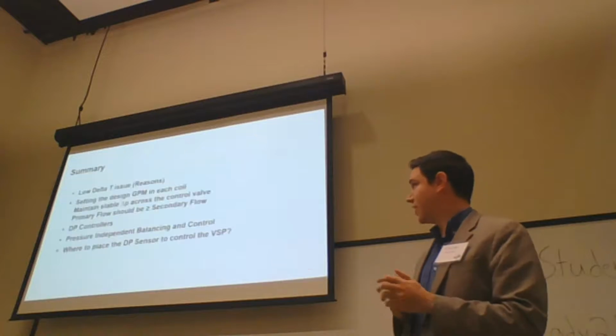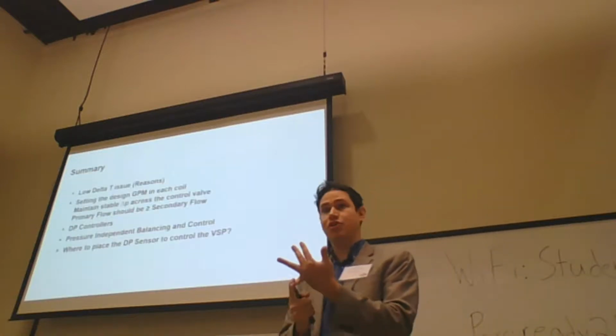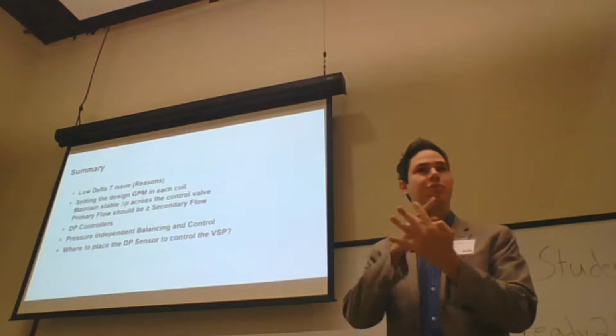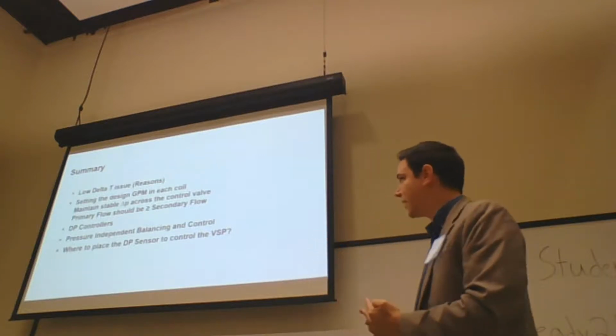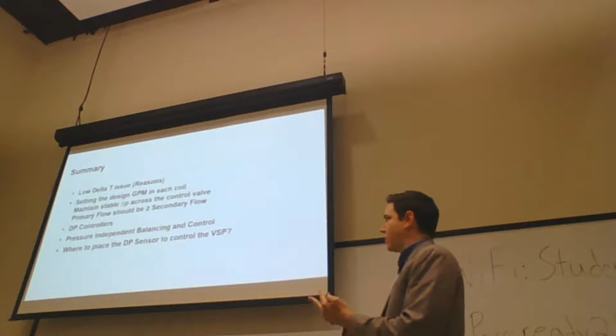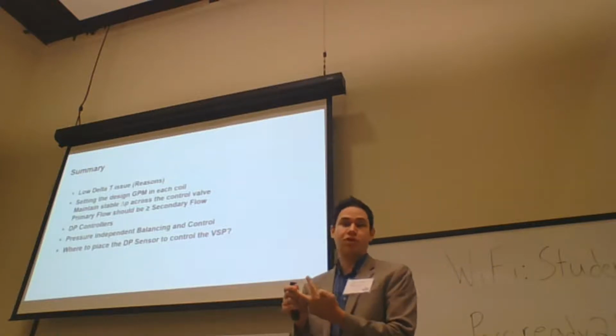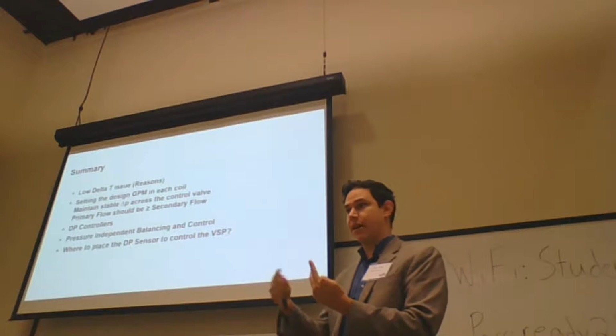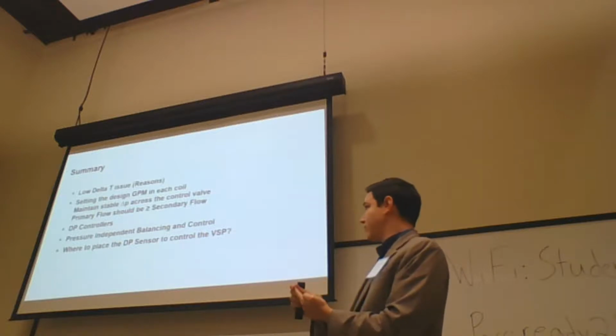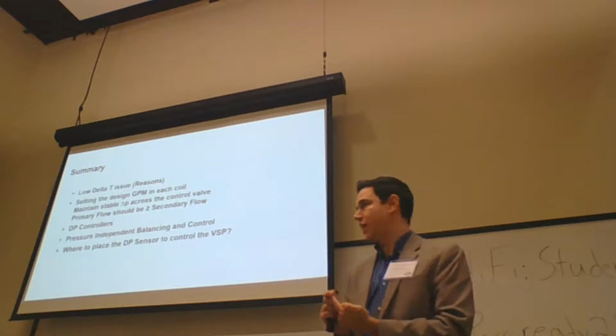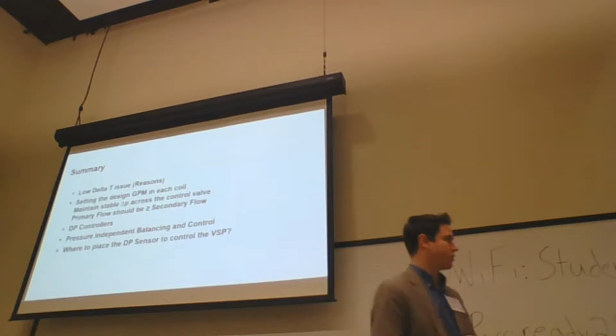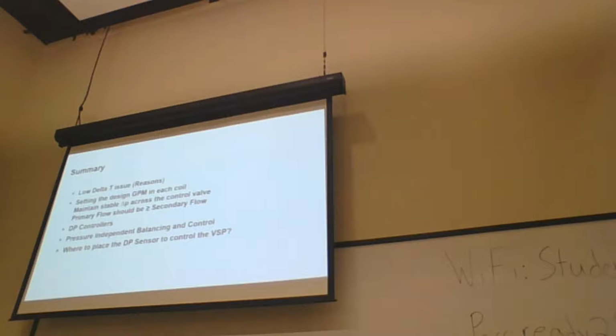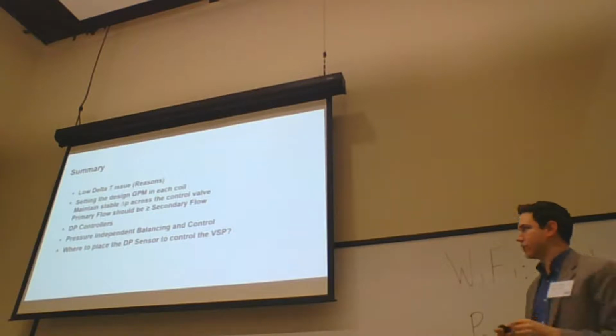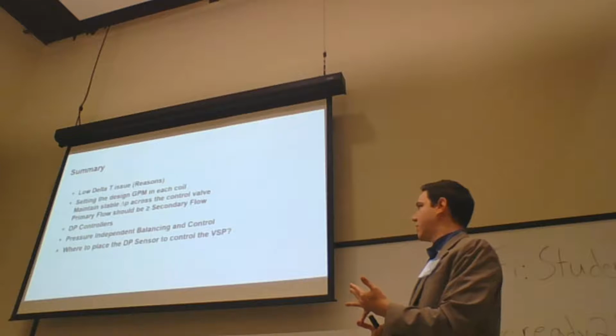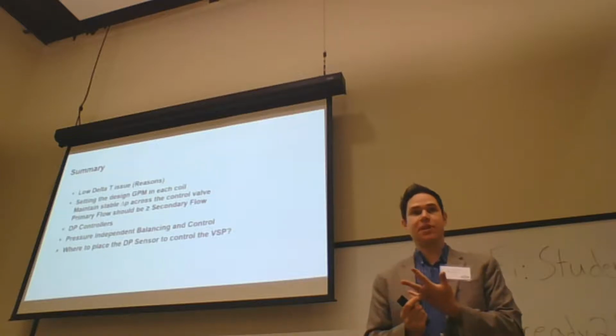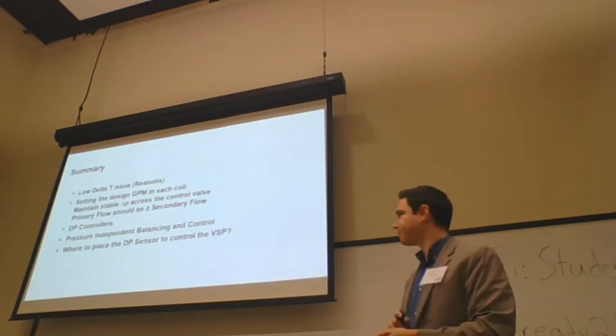And the presentation today is going to be about the low delta T issue reasons. I'm bringing 4 main reasons why we see the low delta T issue. Setting the design GPM in each coil, maintaining a stable differential pressure across the control valve for stabilization. Primary flow should be equal or higher than the secondary flow. Differential pressure controllers, that is this device here in branches or buildings that it could be solved. Pressure independent balancing control valve, and where to place a DP sensor to control the variable speed pump.